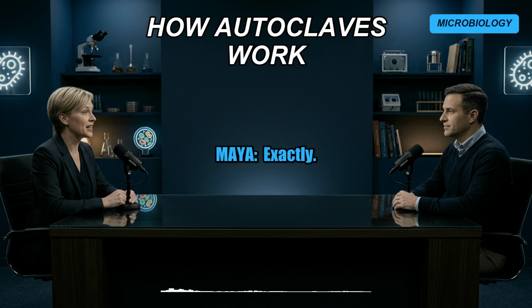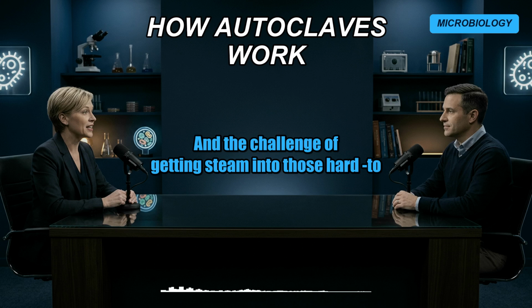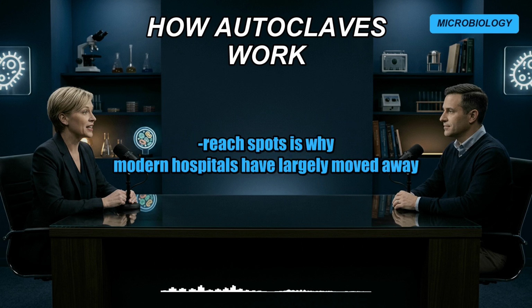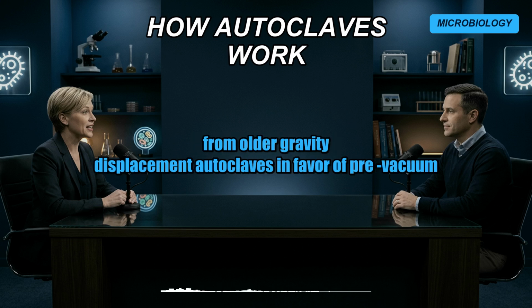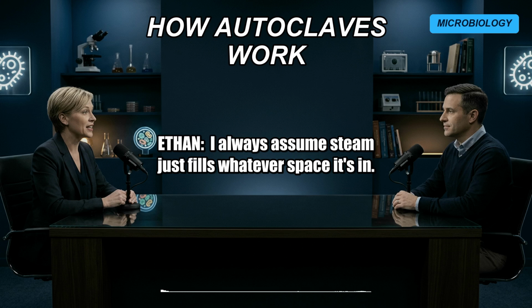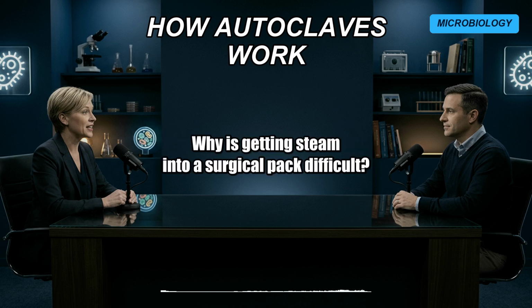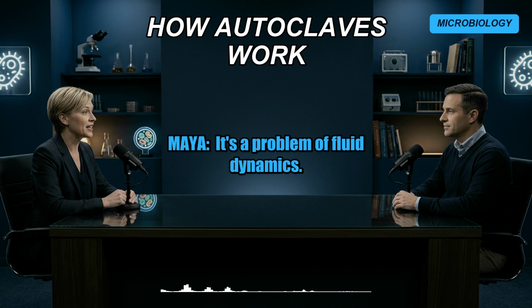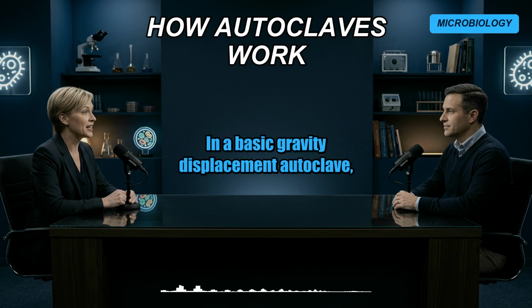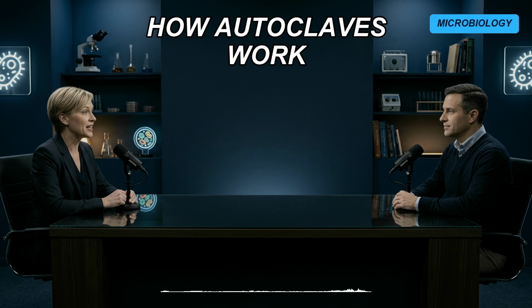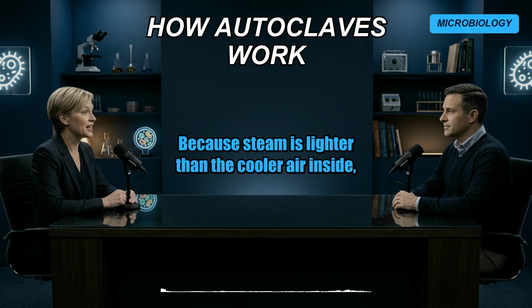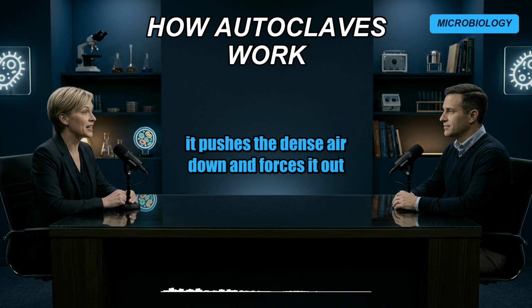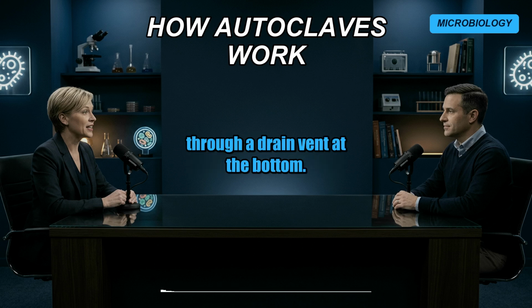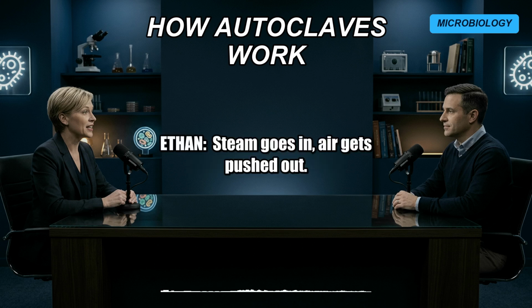Exactly. And the challenge of getting steam into those hard-to-reach spots is why modern hospitals have largely moved away from older gravity displacement autoclaves in favor of pre-vacuum models. I always assume steam just fills whatever space it's in. Yeah. Why is getting steam into a surgical pack difficult? It's a problem of fluid dynamics. In a basic gravity displacement autoclave, steam is pumped into the top of the chamber. Because steam is lighter than the cooler air inside, it pushes the dense air down and forces it out through a drain vent at the bottom. Steam goes in, air gets pushed out.